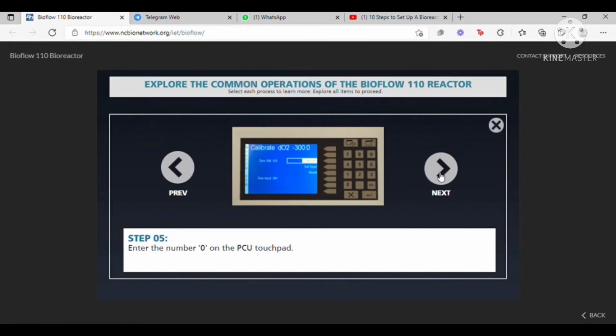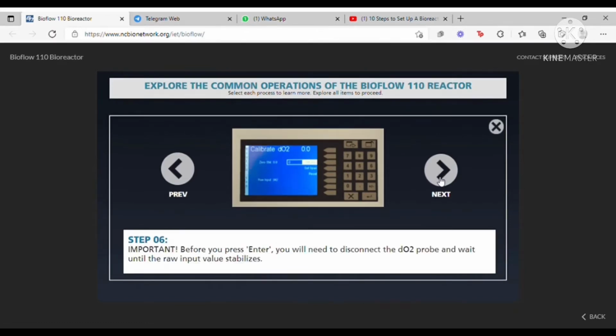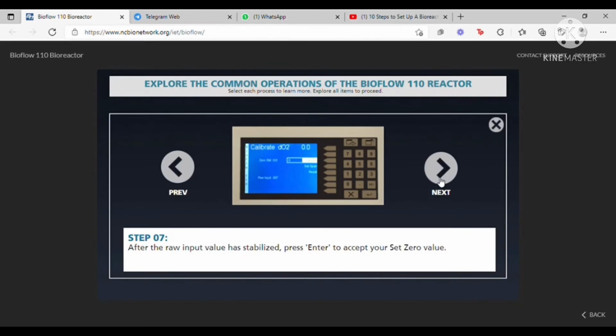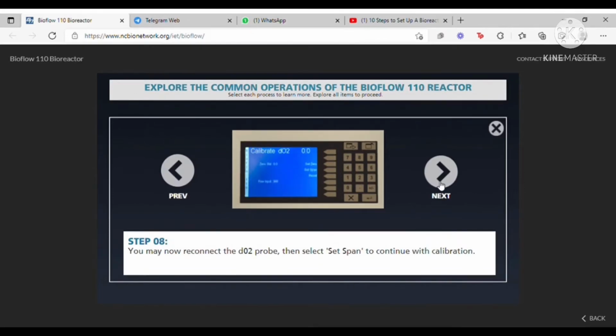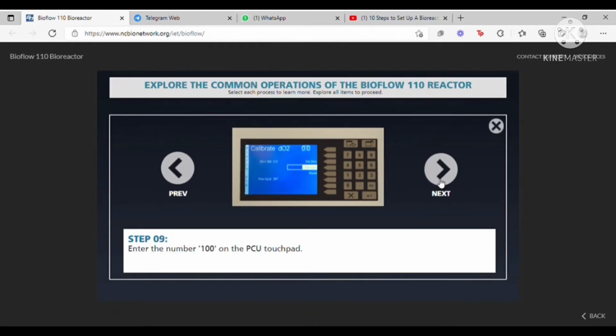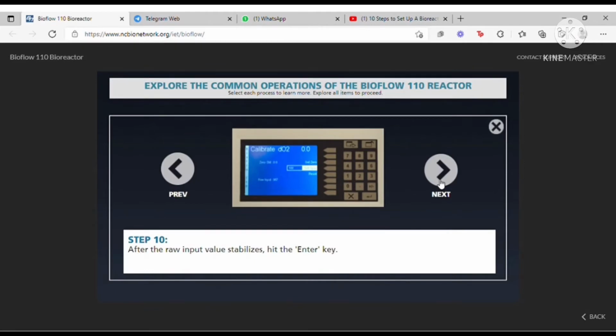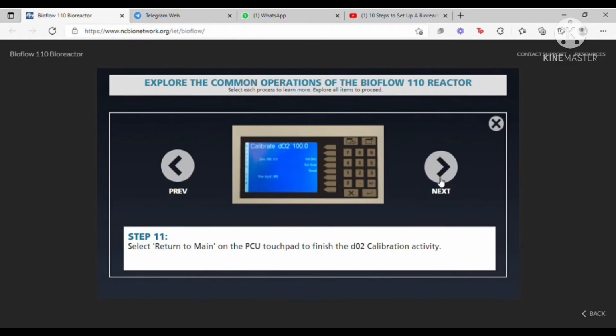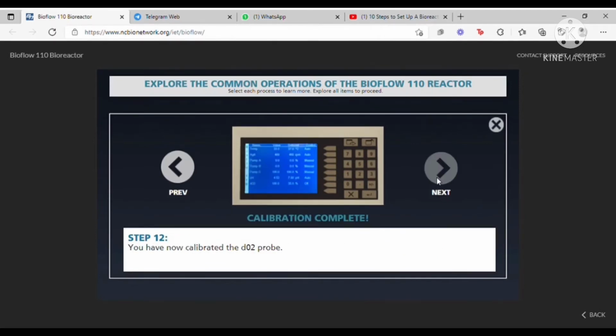Going on with step 4, which would be to select set zero on the PCU touchpad to begin the calibration process. Next would be to enter the number 0 on the PCU touchpad, followed by step 6, which is an important step. Before pressing enter, we will need to disconnect the DO2 probe and wait until the raw input value stabilizes. Step 7 would be, after the raw input value has stabilized, press enter to accept your 0 set value. So for step 8, we will now reconnect the DO2 probe, then select set span to continue. Step 9, we will enter the number 100 on the PCU touchpad. For step 10, after the raw input value stabilizes, hit the enter key. Step 11 would be select return to main on the PCU touchpad and finish the DO2 calibration activity. And lastly, we have calibrated the DO2 probe.